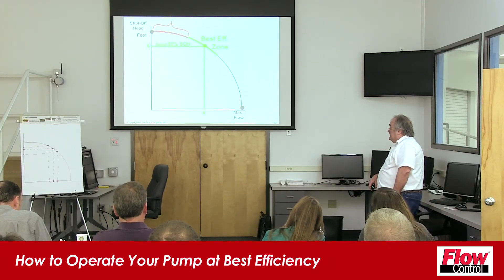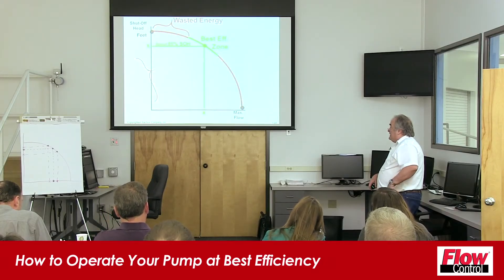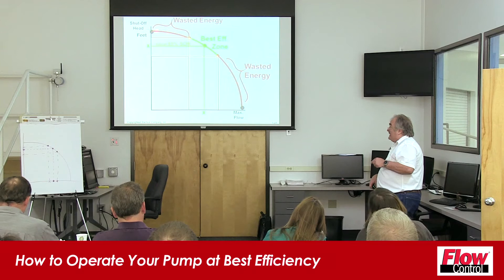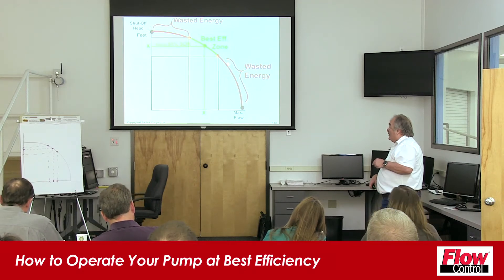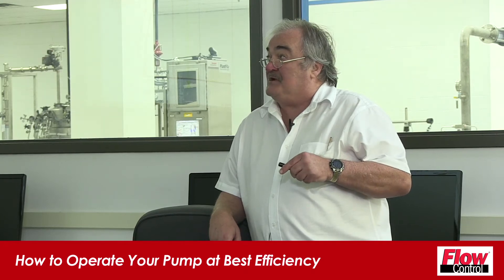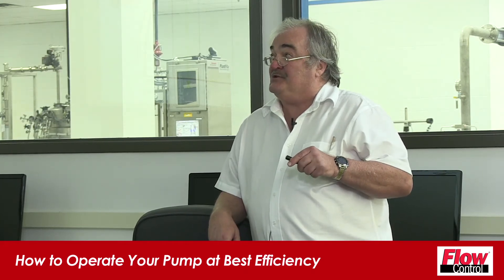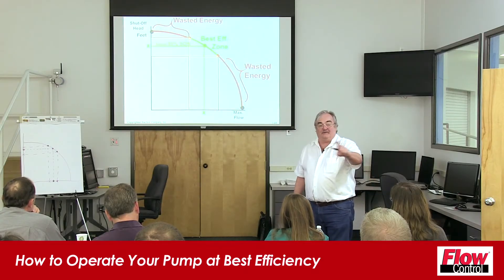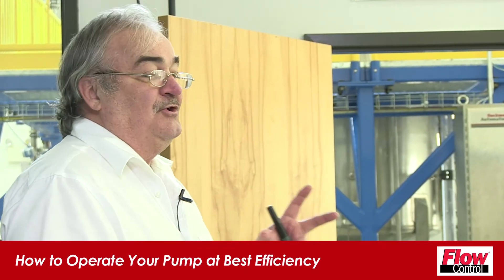You can take a pump curve and find the best efficiency zone — we've been looking at it on some of the pump curves. As the operator or owner of the pump, you should avoid operating the pump outside of this zone, because that is wasted energy.